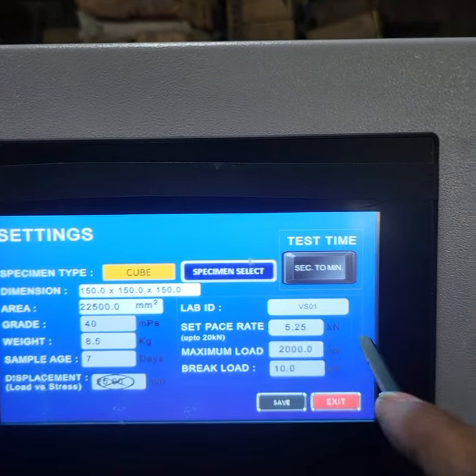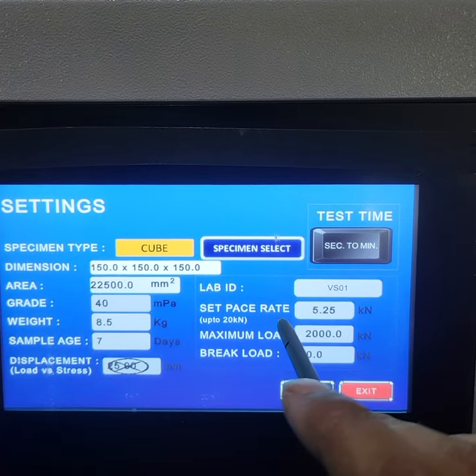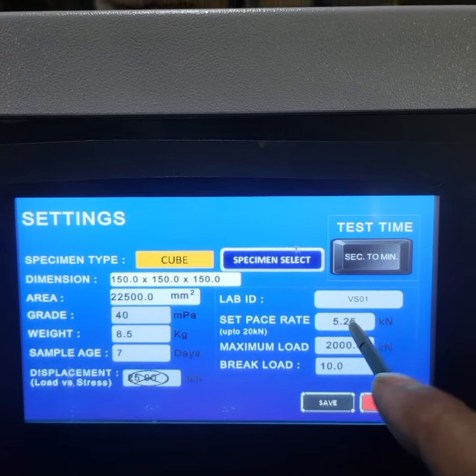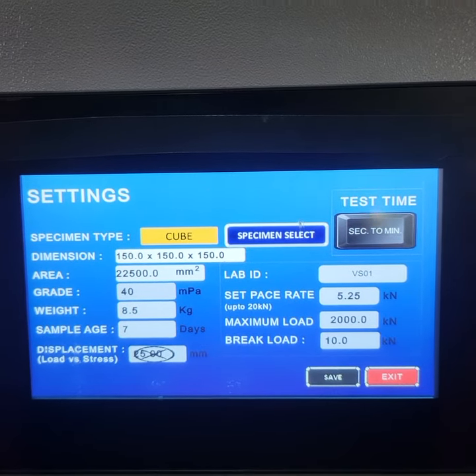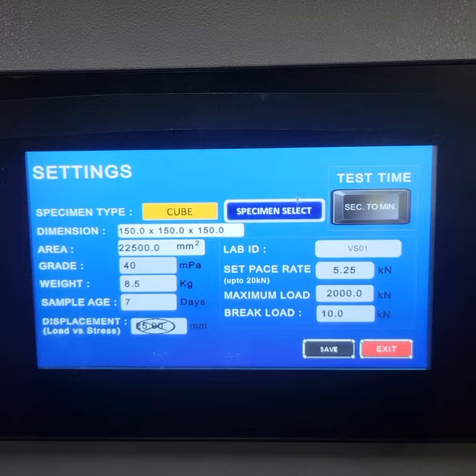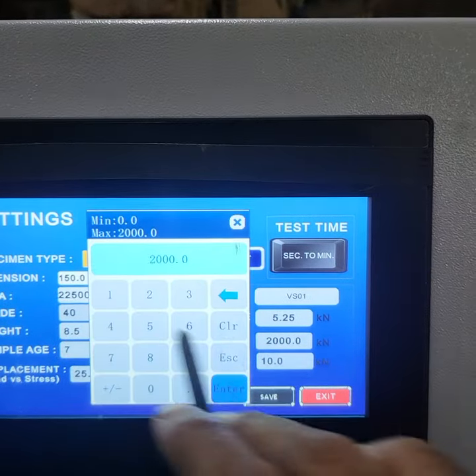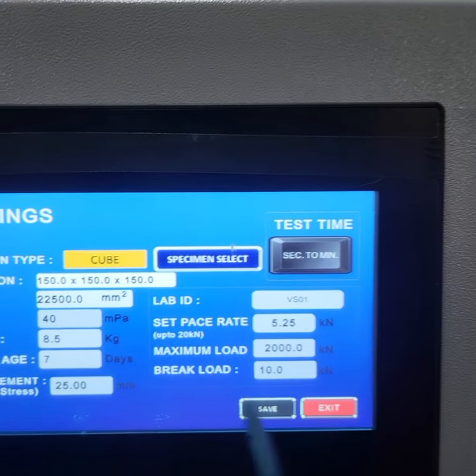The set pace rate is semi-automatic. We have a reference pace rate. We have used the IS standard. The maximum is 2,000 kN. We have protected this with a password. If you want to change the password, enter it on the machine. It will allow up to 2,000 kN or 1,000 kN.